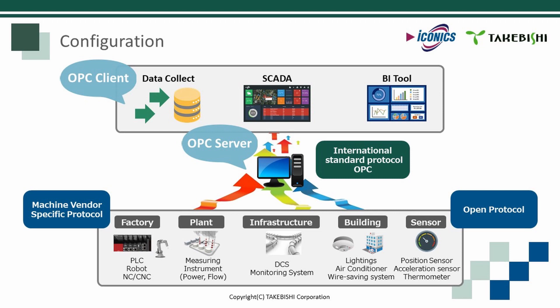OPC is generally used in the following configuration. In OPC communication, a client-server system is used. The OPC server is an industrial communication software product that reads and writes data by connecting to the control device, such as a PLC. On the other hand, OPC clients, like a SCADA product, request data from the OPC server and utilize it in various applications.